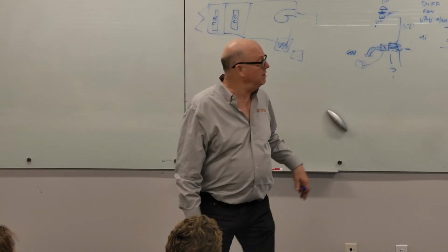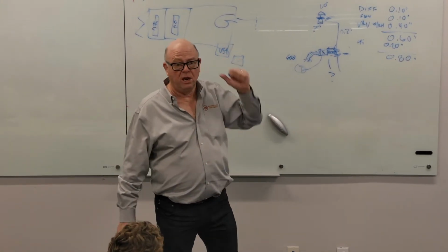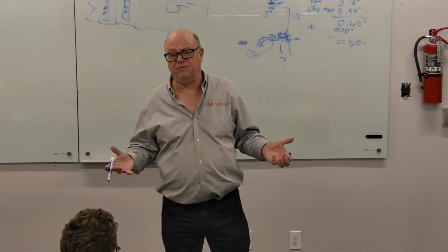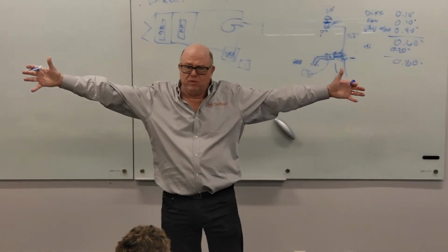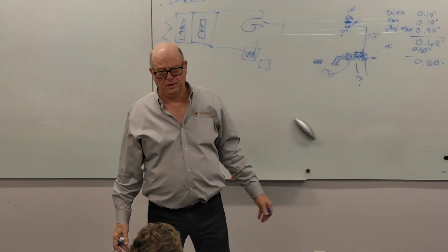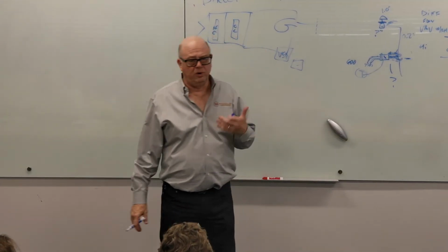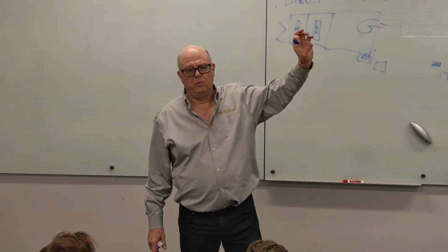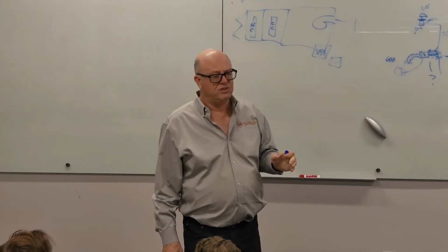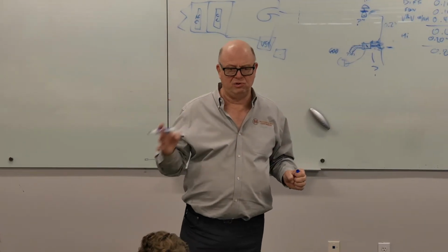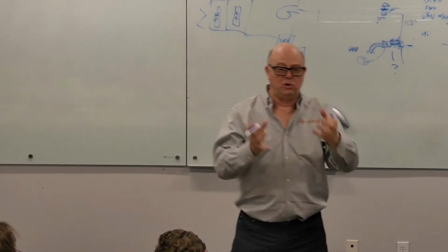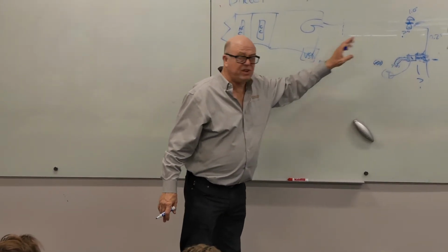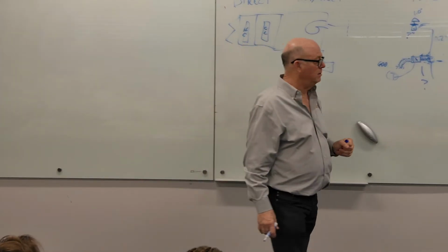Back in the day, we just set it one pressure, and of course you set the pressure for the worst case, and so you wasted a fair amount of energy just pressurizing that duct, more than you ever needed to. Today, if we do it right, and some of this is mandatory with Title 24, and some of it is a couple of different paths you could follow. You could do it this way, or you could do it that way, and either one would be acceptable, okay? But that's how we control those things today.